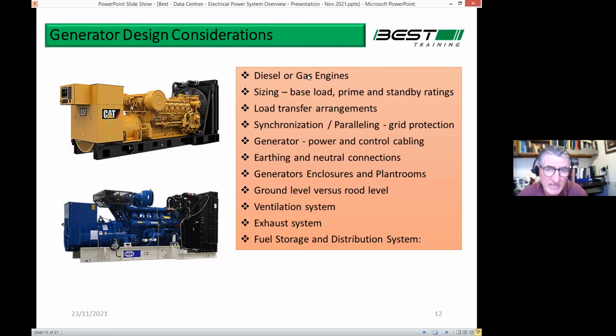Diesels, from an environmental point of view, a gas engine is better than a diesel engine, but there's a lot of disadvantages with the gas engine. Sizing of the generator, where you go base load, prime, or standby rating, is very important. The load transfer arrangement: are you doing a load transfer, or are you synchronizing with the grid? All the generator power and control cabling, how that's done, earthing arrangements. The generator enclosure: do you build dedicated plant rooms? Do you put it on the roof? Do you put it down at ground level, etc.?